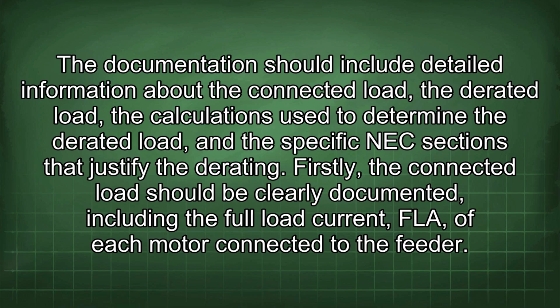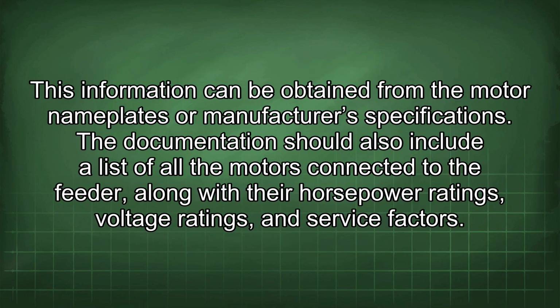Firstly, the connected load should be clearly documented, including the full load current, FLA, of each motor connected to the feeder. This information can be obtained from the motor nameplates or manufacturer's specifications. The documentation should also include a list of all the motors connected to the feeder, along with their horsepower ratings, voltage ratings, and service factors.